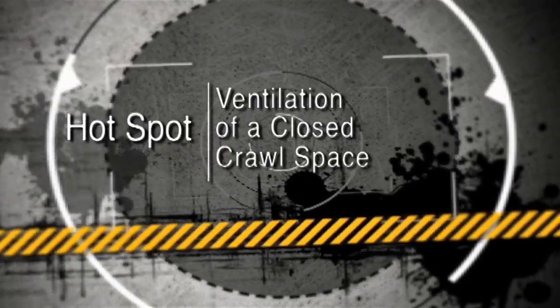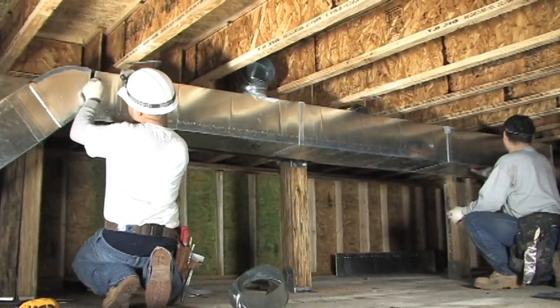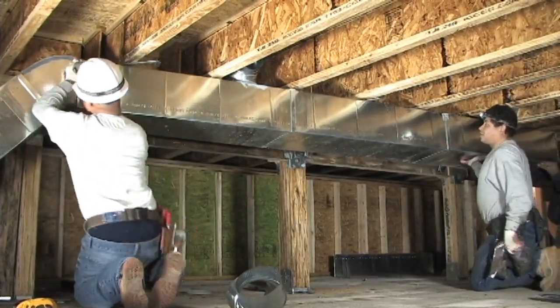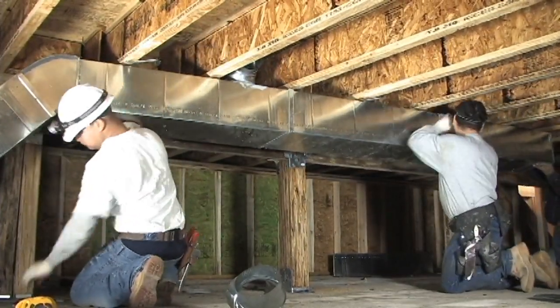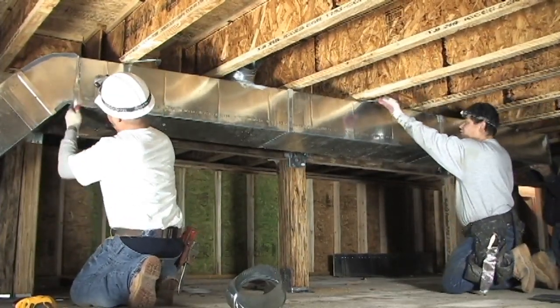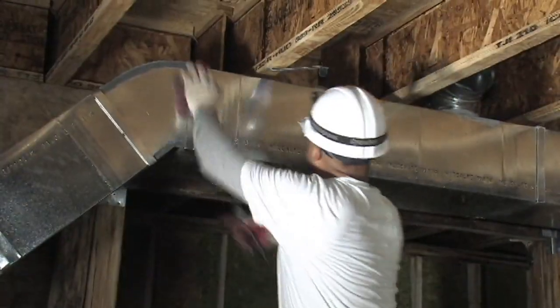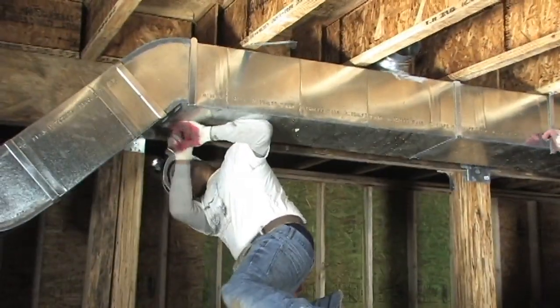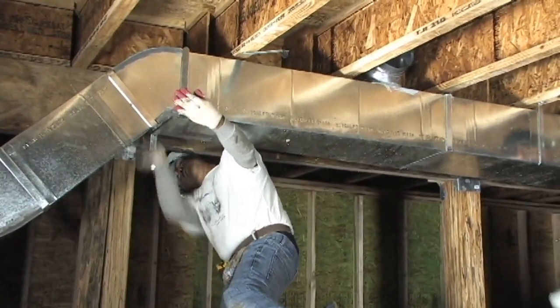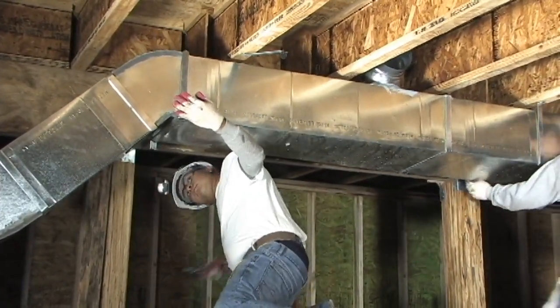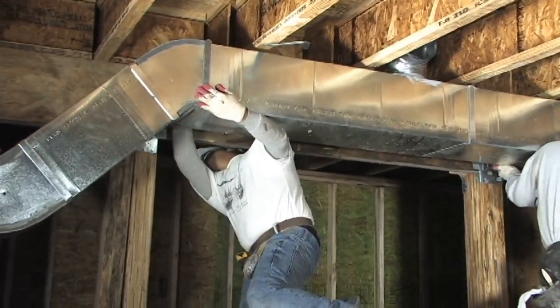Ventilation of a Closed Crawl Space. The International Residential Code requires mechanical ventilation using a conditioned air supply approach or a continuous mechanical exhaust approach. Both approaches require a ventilation rate of one cubic foot per minute for each 50 square feet of closed crawl space floor area, and an air pathway — such as a transfer grill or duct — connecting the crawl space and the house.